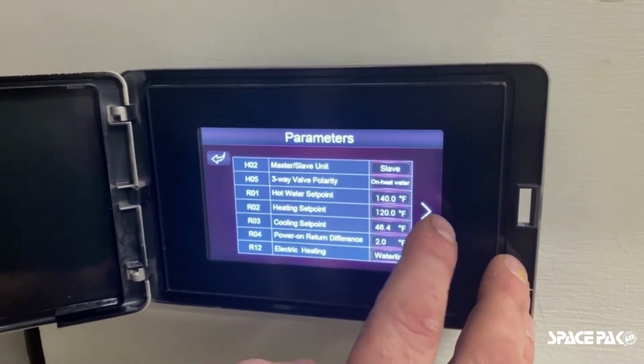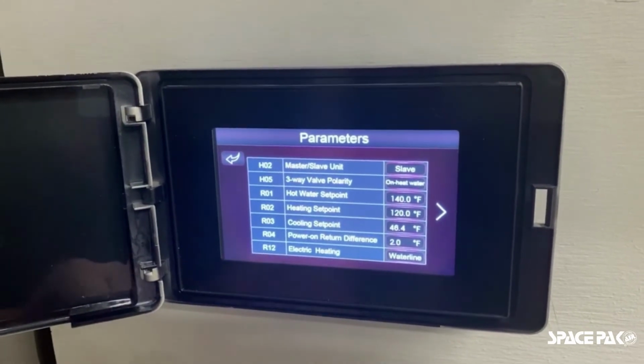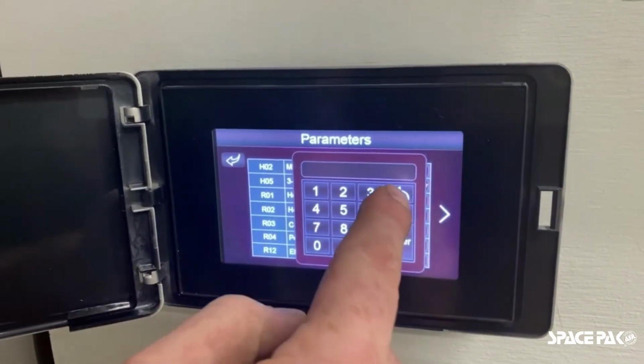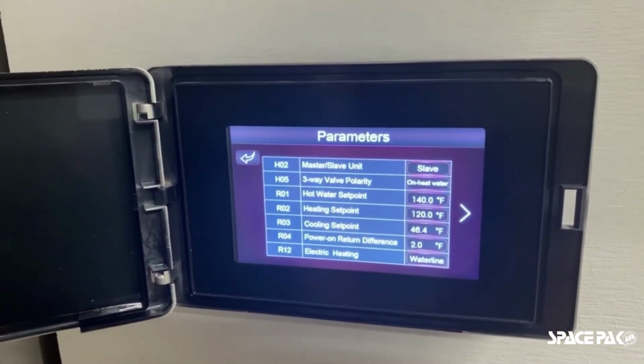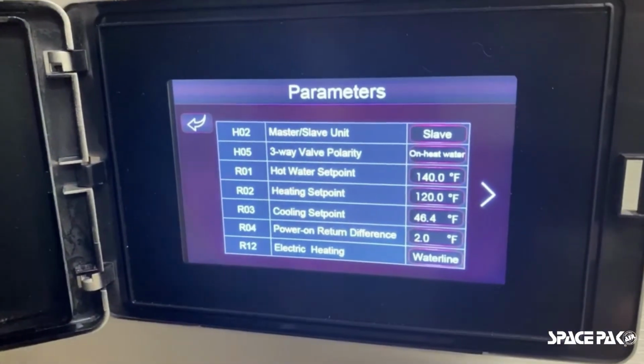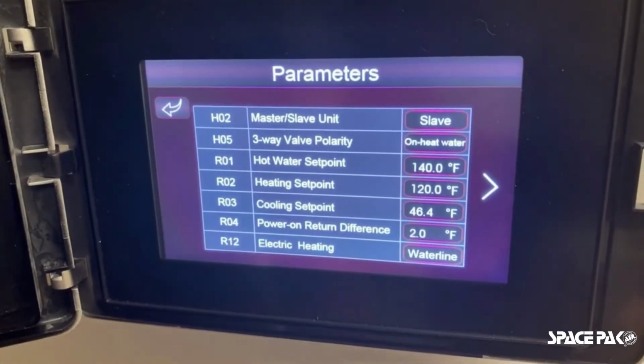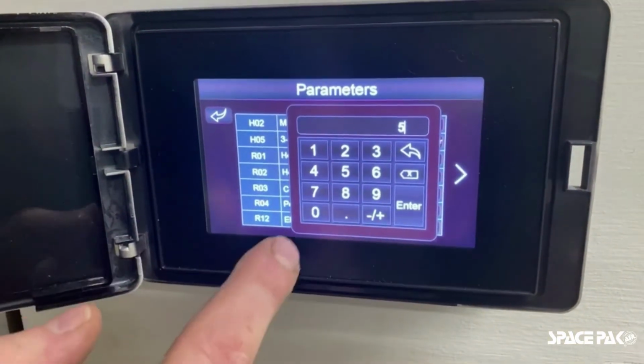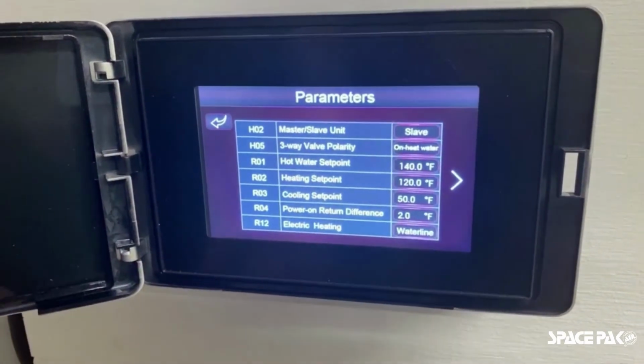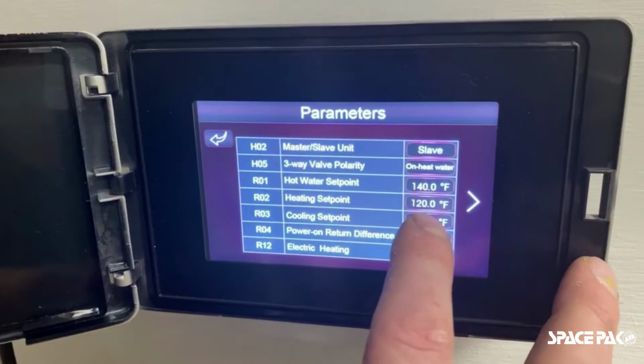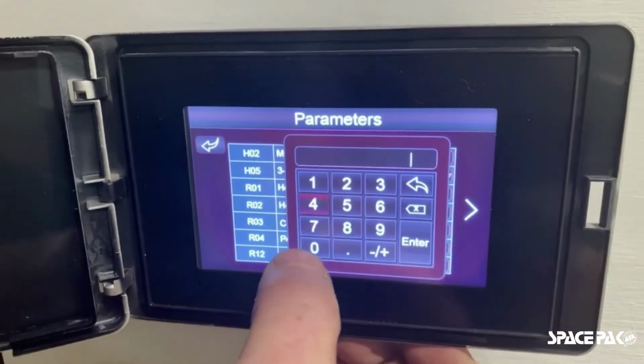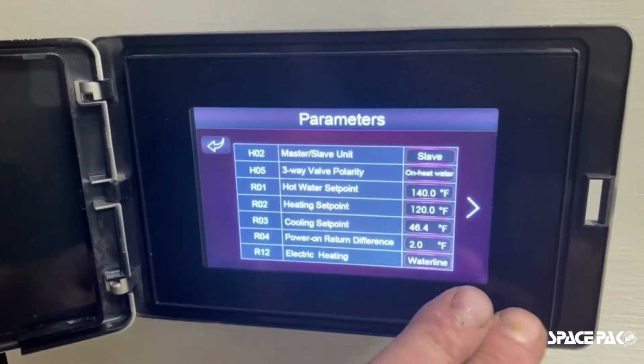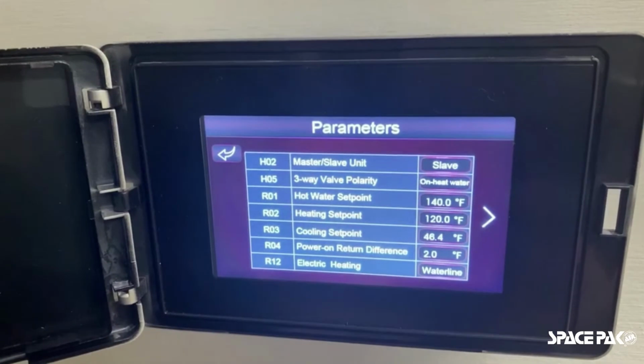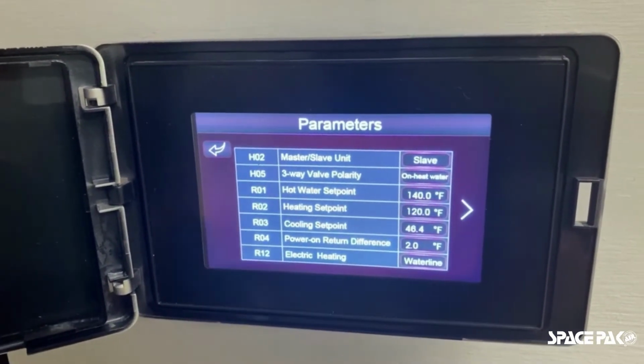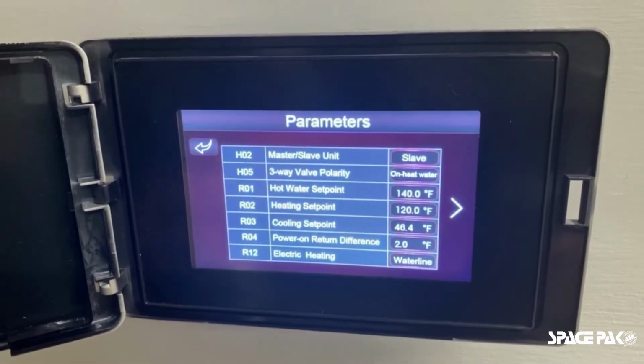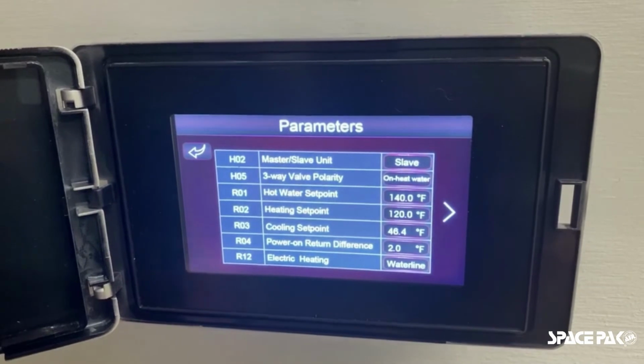Okay, as we cycle through everything else, we have a heating set point and cooling set point. If we look at our cooling set point now, currently it is at 46.4. Understand that the 46.4 is the return water temperature, so we're actually discharging much colder temperature. But if we wanted to say, I'm going to make my return water temperature 50 degrees, enter. That's where we're going to be. If we say, let's make it 40 degrees, press enter, it's just going to drop it down to the lowest point, which is that 46.4 degrees on the return water temperature. And generally, depending on flow rate through this inverter driven unit, we are going to deal with anywhere between a 4 and a 10 degree water delta. So keep that in mind.